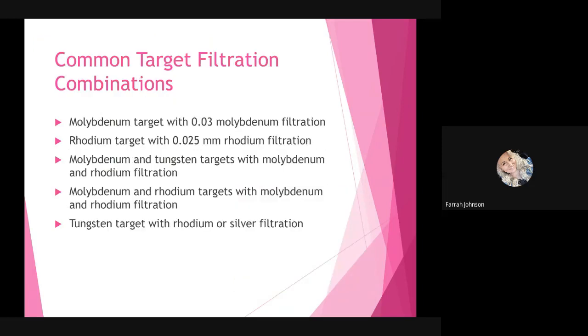Now, the common target filtration combinations are as follows. A molybdenum target with a 0.03 molybdenum filtration. For machines with a rhodium target, they can have a 0.025 millimeter rhodium filtration. It's common to see molybdenum and tungsten targets with both molybdenum and rhodium filtration. You can have molybdenum and rhodium targets with molybdenum and rhodium filtration. And then you can lastly have a tungsten target with rhodium or silver filtration.